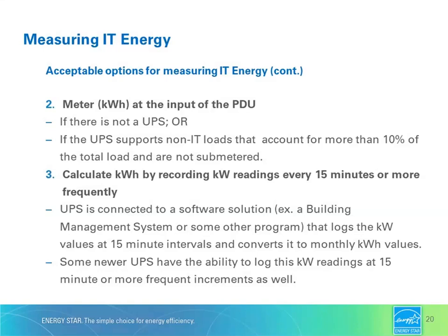Instead of using a kilowatt-hour energy meter, you can use a software solution connected to your UPS that will record kilowatt power readings at intervals of 15 minutes or more frequently. And then you can use those kW power measurements to calculate the kWh energy use. Kilowatt power measurements themselves will still need to be taken at the UPS output. And again, we'll cover this more when we talk about special cases.